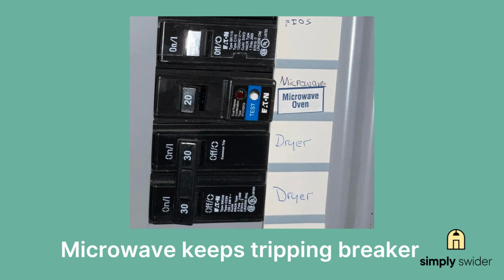And here's the key thing. This crowbar circuit safety design means when things go wrong, they go wrong dramatically. That violent breaker trip isn't necessarily a sign of major damage. Often it's just a $5 switch doing its job to protect you.